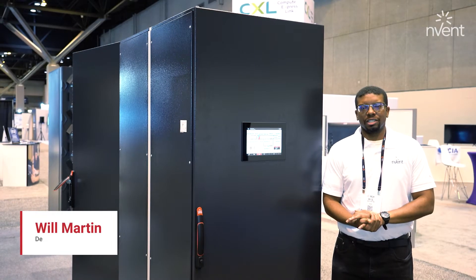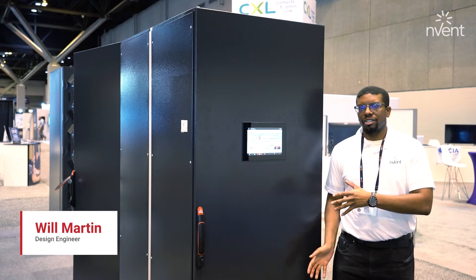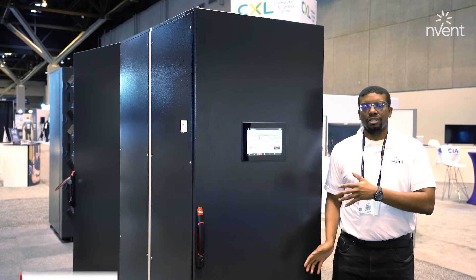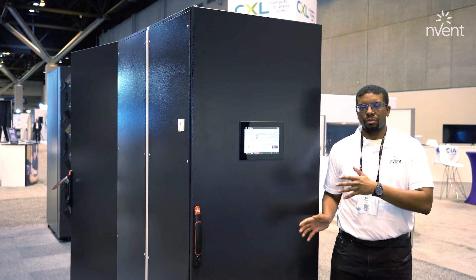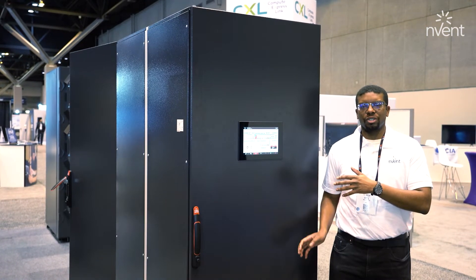Hello, I'm Will Martin, a design engineer with nVent Hoffman, and this is our Rack Chiller CDU 800. This unit has 800 kW of cooling capacity at a 4K approach, and it provides 950 liters per minute at a 45 PSI pressure differential.